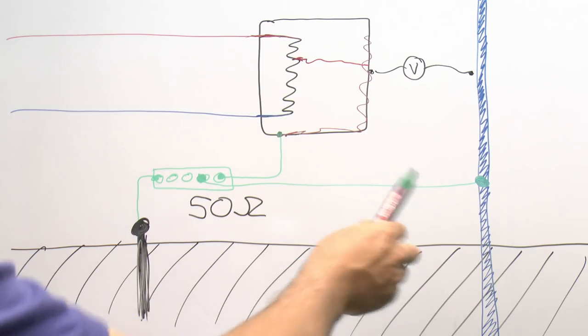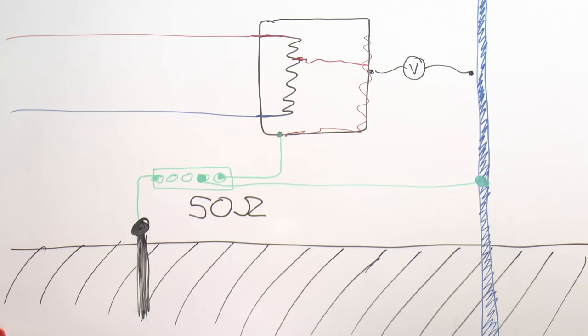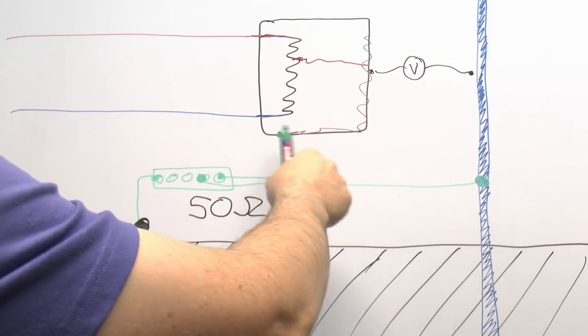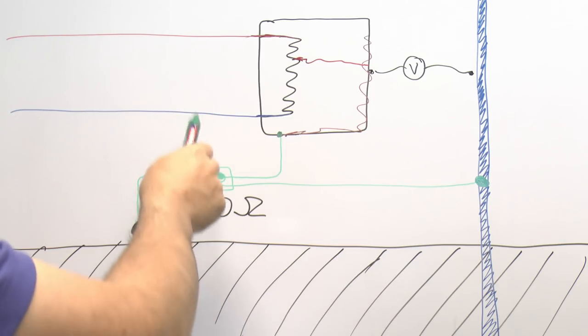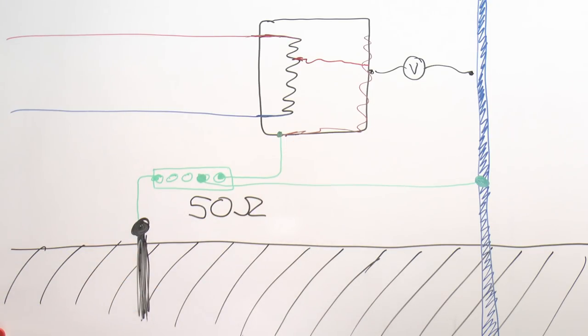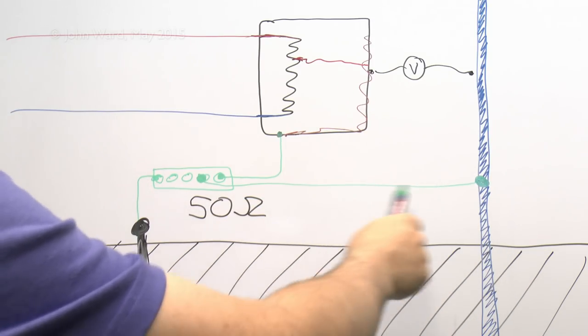This is why when installing any electrical equipment it's important to ensure the main bonding is installed and electrically continuous. Without it there's a good chance extraneous and exposed conductive parts will have different voltages, and that's when you get a shock from, say, holding a cold tap while touching a water heater. Note that an RCD in the circuit will disconnect the supply in the event of such a fault, but for the duration — perhaps 0.2 seconds — before it disconnects, you still have that dangerous voltage appearing if the main bonding is not installed.